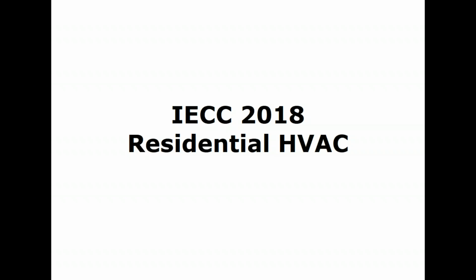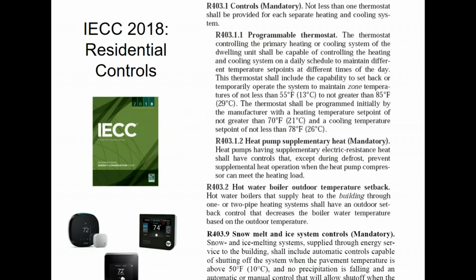So specifically, the residential provisions as related to HVAC for the 2018 IECC and hence the Indiana State Code. From the control standpoint, programmable thermostats are mandatory. You are not allowed to legally install a non-programmable thermostat. I understand people do that. I get it. But everything has to be a programmable thermostat. Some older versions of IECC had exceptions for radiant systems. Those exceptions no longer exist. So literally everything that has a thermostat that you put on it, that thermostat has to be a programmable thermostat. So you shouldn't even have non-programmable ones on your trucks anymore.